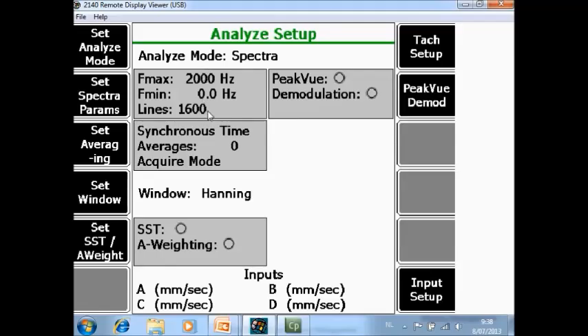From 0 to 2000 Hz, 1600 lines, Synchronous Time, Average is set to 0, that means he will collect data till the user stop the averaging process. And 4 sensors are active. So I will start the machine.